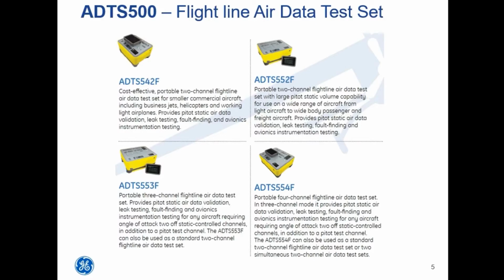So the 542 will control into 3 litres of volume quite happily. Modern aircraft today, some have very small internal volumes, like old 747s. So it will get there and maintain the rates. Obviously, if we're outside its volume capability, then it will get there, but may not be able to achieve the rate of climb. But that's one of the payoffs. Another advantage, for helicopters for example, is that we've got a low speed, better calibration for low airspeed testing.